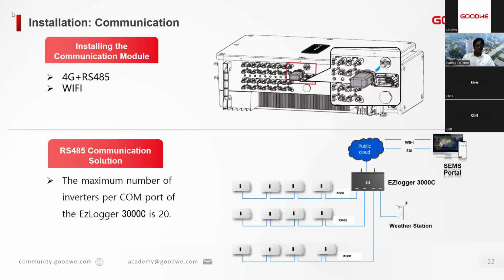As I mentioned, we have the Wi-Fi dongle that is provided in the box with the inverter. Therefore, in terms of communication, you can do either the Wi-Fi, the 4G, or also the RS485 in case you're using the controllers, which we have as the EZ Logger or the SEC1000. The SEC1000 and the EZ Logger can support up to 60 inverters with 20 inverters per port. Therefore, you will be daisy chaining 20 inverters for one port and it has 3 COM ports.